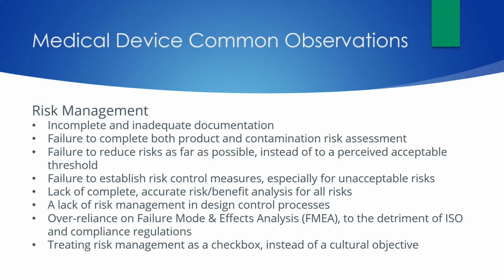Another area, failure to complete both product and contamination risk assessment. Inspectors observed vermin, such as bird and insects, in the facility near open equipment used for manufacturing. Failure to reduce risks as far as possible. So a surgeon implanted a stem that was wrongly sized because there was no tool available to determine the size needed. This resulted in an unstable implant. X-ray templates were provided for every other implant size. It is not reasonable not to provide templates for each size. An economic impact should not be considered if this can reduce risk.